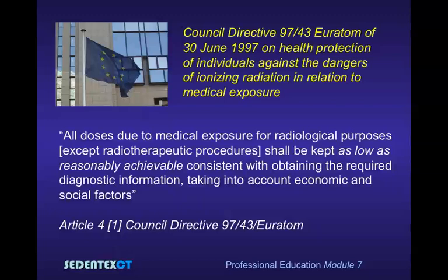The Council Directive 97/43 Euratom on health protection of individuals against the dangers of ionizing radiation in relation to medical exposures stated that all doses due to medical exposure for radiological purposes, except radiotherapeutic procedures, shall be kept as low as reasonably achievable, consistent with obtaining the required diagnostic information, taking into account economic and social factors. The key phrase here is as low as reasonably achievable. This is commonly referred to as the ALARA principle.